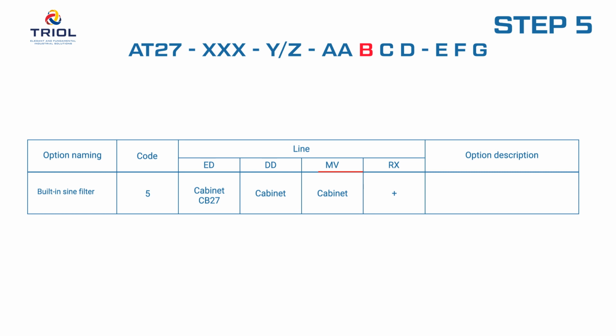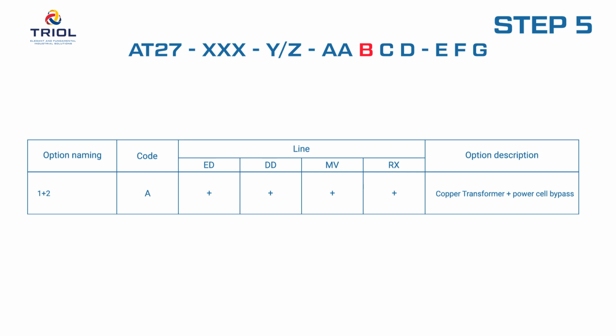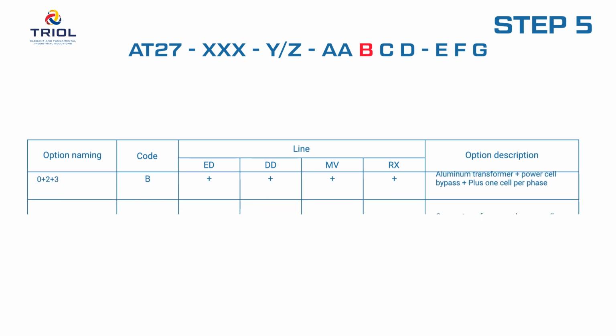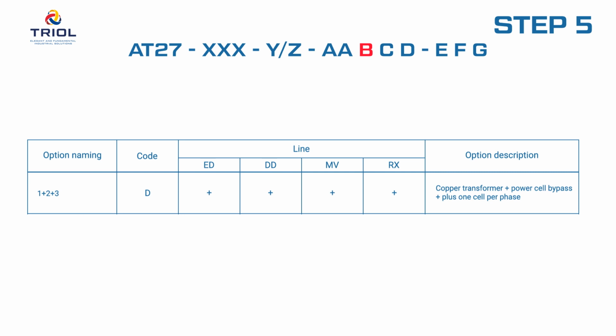In addition to the listed single power circuit options, various combinations of power circuit options are available in the AT27. Each available power circuit option has a unique designation. Choose the one that suits you. For example, when ordering a frequency drive with a set of power circuit options, transformer with copper windings, option designation 1. Bypass of power cells, option designation 2. Plus one cell per phase, option designation 3. We get a combination of power circuit options. 1 plus 2 plus 3 equals D.